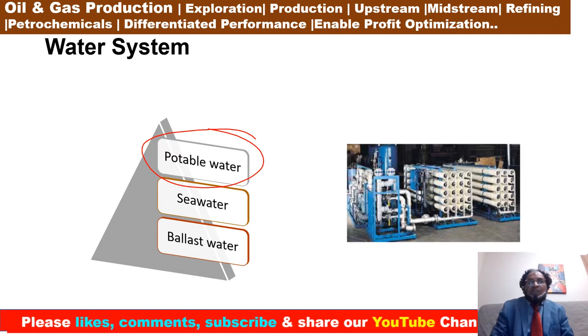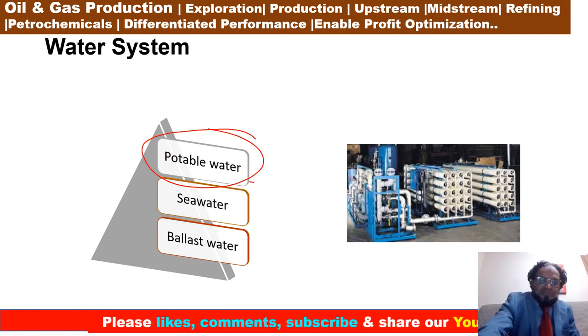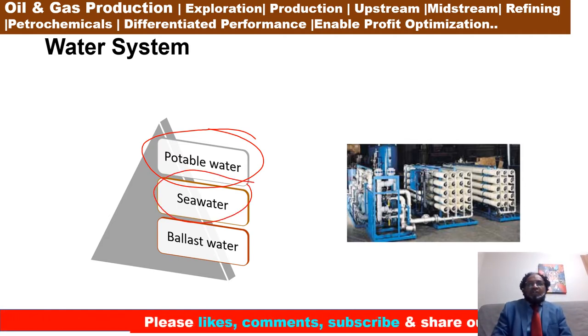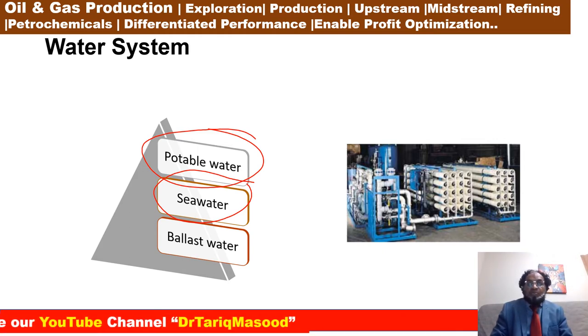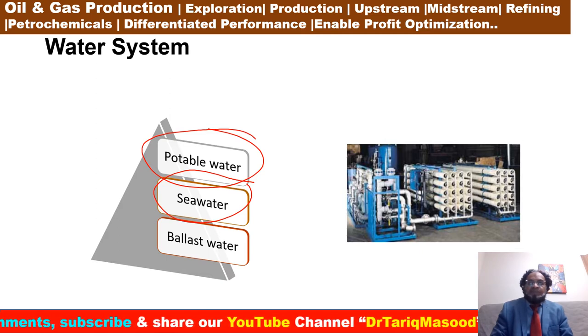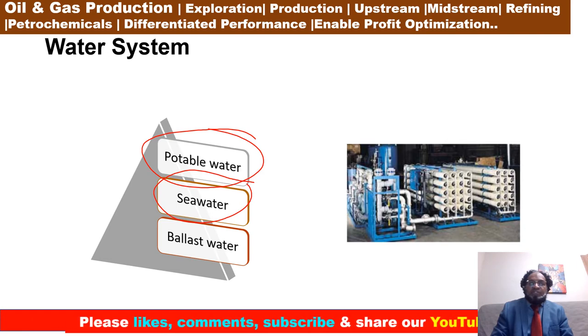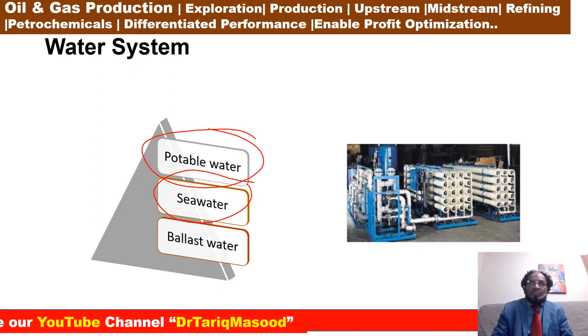Now, next is seawater. Seawater is used extensively for cooling purposes. Cooling water is provided to air compressor coolers, gas coolers, main generators and the HVAC system. In addition, seawater is used for the production of hypochlorite. And for the fire water, seawater is treated with hypochlorite to prevent microbiological growth in process equipment and piping. Seawater is sometimes used for reservoir water injection.